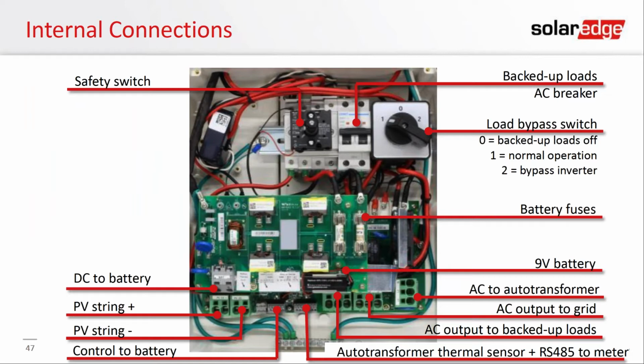So here's what the inside of the StorEdge connection unit looks like. And as you can see, there's a whole bunch of awesome, cool, fun things in here. One thing that is important to note that you can't very visibly or clearly see is that there is actually an auto transfer switch. So I get this question a lot: okay, when the inverter goes into backup mode, does it disconnect from the grid?